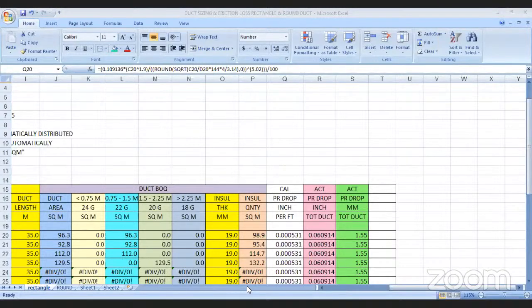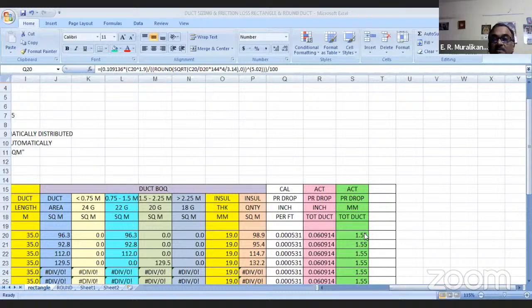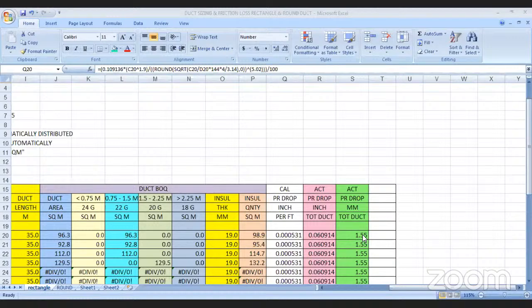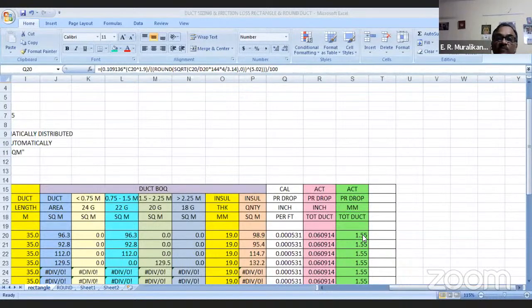How to size a plenum? How to calculate friction loss in masonry duct and in underground mine walls? See, everywhere it is the same thing. Only the friction factor varies. For GI you have some friction, for cement you have some other friction. You have a coefficient, and if you put in the coefficient, you'll know. That's it. The formula is the same. The coefficient varies.